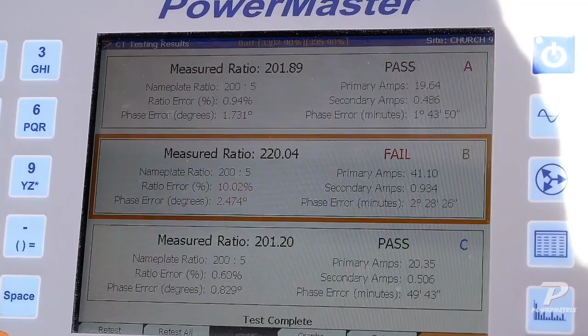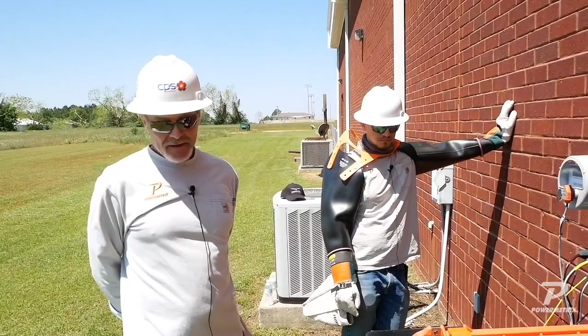Nope, it's consistent at 10% ratio error on B phase. So at this point, we start looking towards the CT. We may need to check that CT on B phase, because we don't think it's any of our connections between the machine and B phase. So this is where we've started trying to eliminate, is it us or is it the installation? And so far, wouldn't you agree, it's not looking like us.